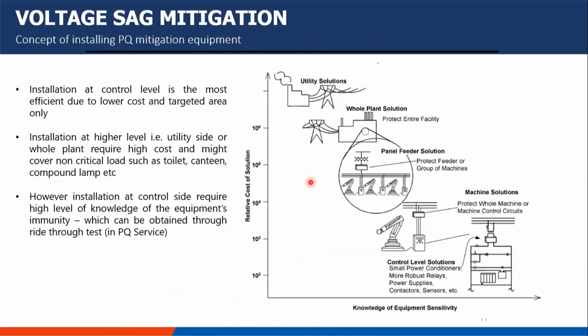When we talk about mitigating voltage sag, we always talk about PQ mitigation equipment, such as UPS systems or any other equipment in the market. But you can see here the cost of the solution, which is 10 to the power of 2, 10 to the power of 3, with low knowledge of equipment sensitivity. For a utility solution, for example, if the utility wants to install mitigation equipment, it will be very high cost because the utility will cover all the load, which includes maybe the toilet, the canteen and the compound, which are non-critical when a voltage sag happens. So the lowest cost will be at the machine solution or control solution, somewhere here.